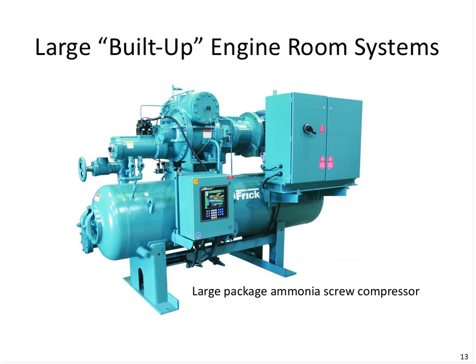So here's what we might find in the large engine room. I want to point out a couple things on this compressor in particular. This is the electric motor, the variable frequency drive inside of this cabinet right here. Here's where the screw rotors are. And then of particular interest, this is the slide valve. Slide valve is utilized to allow the refrigerant that's entering the compressor to be released back to the suction, which is a means of unloading this compressor.